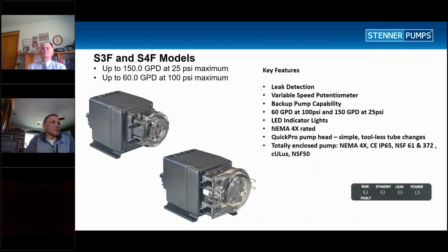Now we have two different versions. We have the fixed rate version, which we see here, and you'll notice over here the display will show a run signal, which will be green. It'll turn red if it starts to fault. You can put the pump in standby mode. It'll tell you if there's a leak, and it'll also tell you when there's power. So it's just some basic controls, and then the pump itself would connect to a control system.